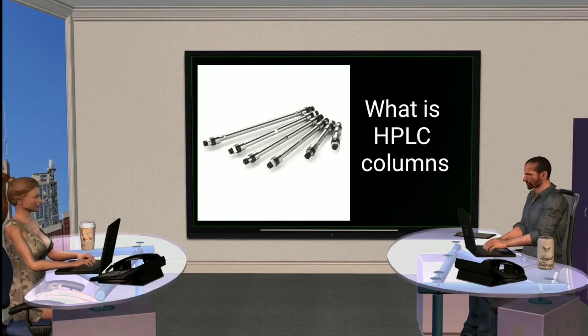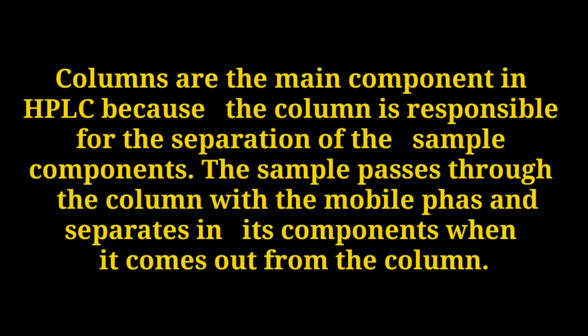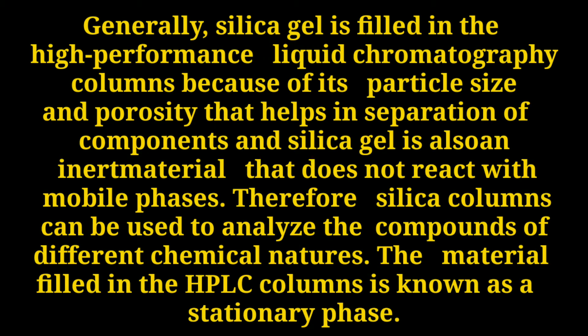Today in this video I am going to tell you about HPLC columns — what is an HPLC column and how many types of HPLC columns there are. Columns are the main component in HPLC because the column is responsible for the separation of sample components. The sample passes through the column with the mobile phase and separates into each component when it comes out. Generally, silica gel is filled in the HPLC column because of its particle size and porosity that help in separation of components. Silica gel is also an inert material that does not react with the mobile phase, therefore silica columns can be used to analyze compounds of different chemical nature. The material filled in the HPLC column is known as the stationary phase.